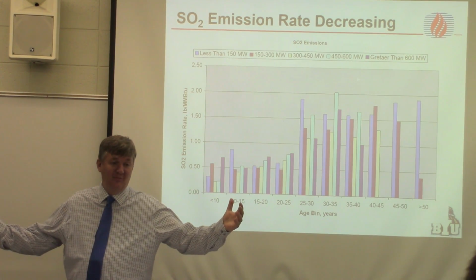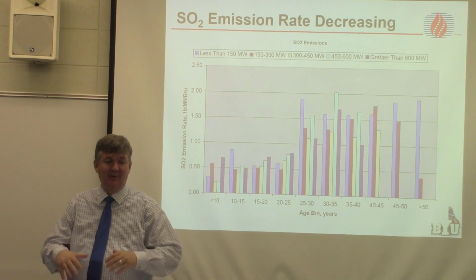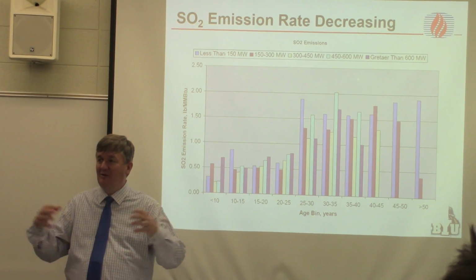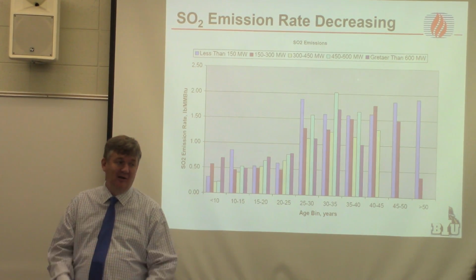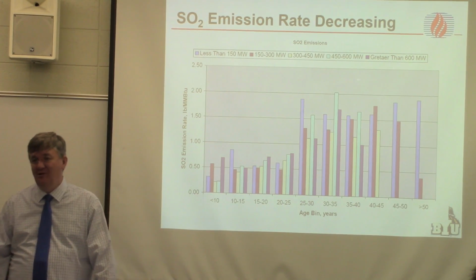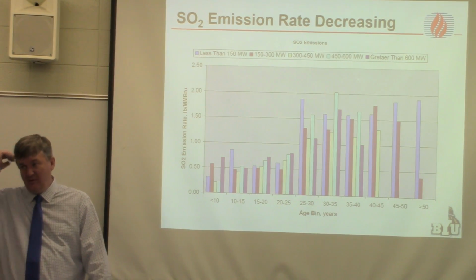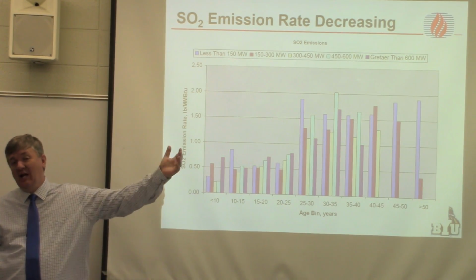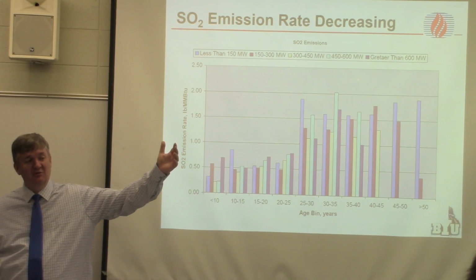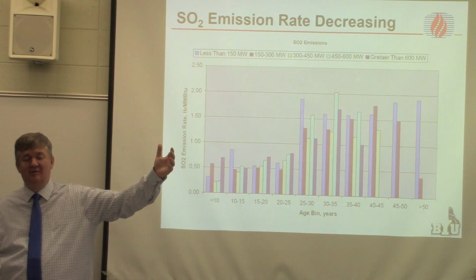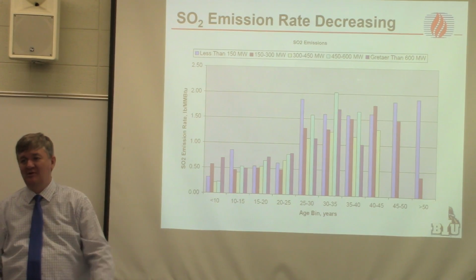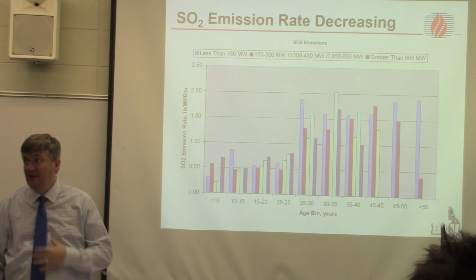Part of what you have to do is build a system that can operate at that low pressure without air leaking into it. Getting air into the steam causes serious corrosion problems all the way through the boiler. So it goes from very high pressure to quite low pressure, and the pressure ratio is much larger than 250 because of the low pressure inlet on the system.